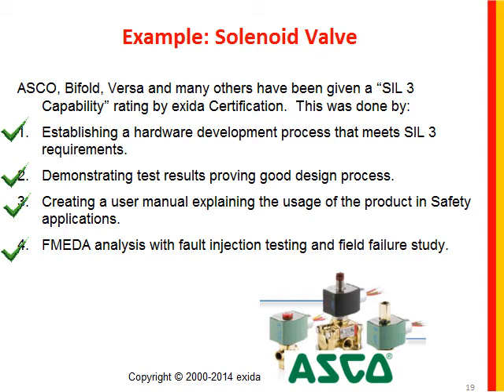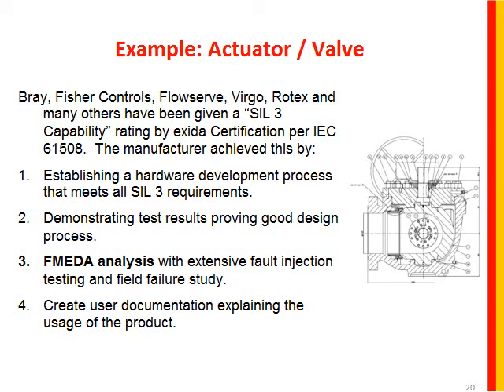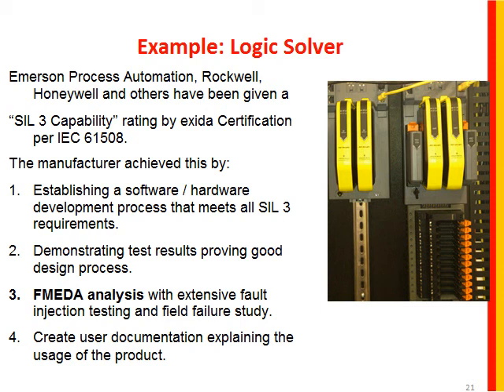We cover both random and systematic failures because those are the two fundamental principles of IEC 61508. Actuators and valves have been certified — a lot of people ask whether mechanical parts are part of 61508, but yes, they are; they're part of a safety system, and there is a clear statement that this includes all parts of a safety instrument and function that has electrical, electronic, or programmable electronic components. We look at the design process, testing results, and perform a detailed FMEDA analysis that provides reliable, accurate failure rate data — along with user documentation — to cover both systematic and random failures.